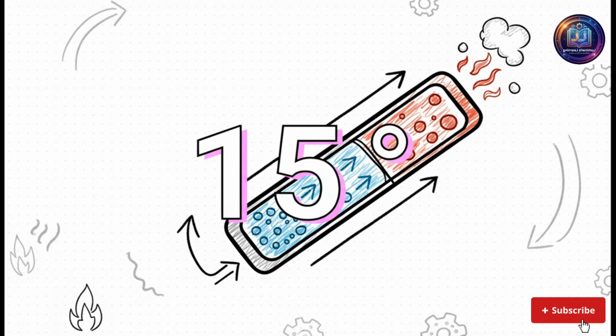And really, it all comes back to this one number, that simple 15-degree incline. It seems like such a minor detail, but it is the secret sauce. It's what enables the entire process of natural circulation. Without that specific angle, the density difference between the hot and cold water just wouldn't be enough to drive the flow. A simple geometric choice powers the entire system.